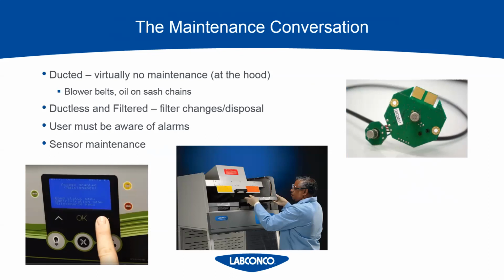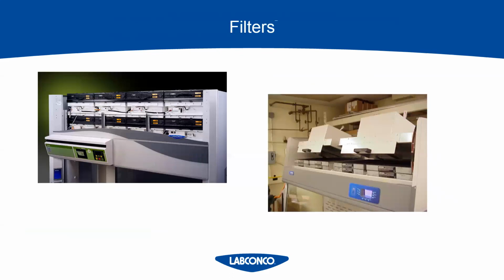Filters have a cost and a maintenance requirement, like we just spoke about. Depending on what type of ductless hood you have, the filters could range anywhere from a couple $100 to $1,000 each. And each hood can have anywhere from 2 to 10 filters. So the most that you're going to be spending on a hood would be 10 times $1,000. You could be spending $10,000 just on filters.